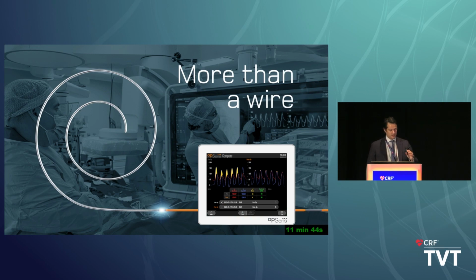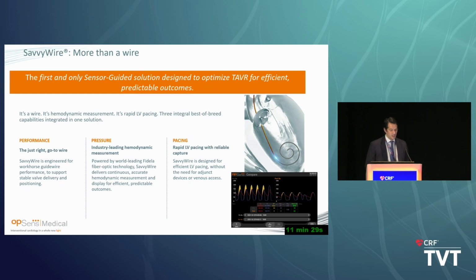So that's the device, the SavvyWire, and this is the console. You can see you have a wire with a console that can display, and you can put it on your big screen also if you want, that displays the pressure gradient before and after. And it's very useful and very convenient. So the SavvyWire, they like to call the 3P. First, performance. This is, like I said, a very good wire with good characteristics, very robust, and allows you to deliver a valve in every type of anatomy. I did a lot of complex cases with horizontal aorta, Evolut 34. It's very useful, very stable.